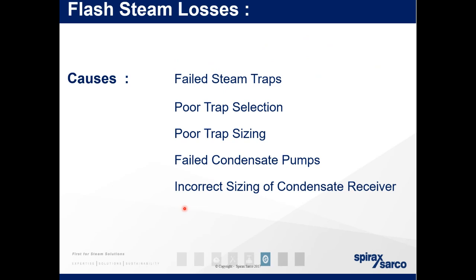So I'm thinking of something we looked at the other day. They have washrooms relatively close to where they're venting some flash steam. By adding a flash steam recovery vessel and then combining it with a CIP line, which is currently going to drain, we can then use that for a water-to-water heat exchanger and heat water for washrooms.